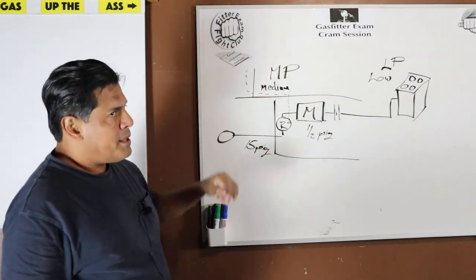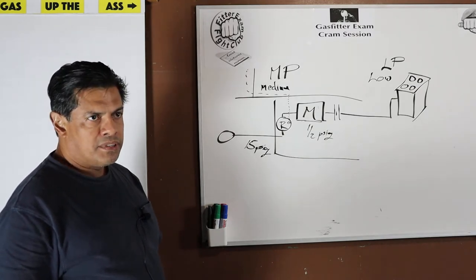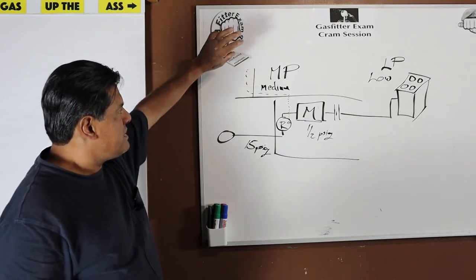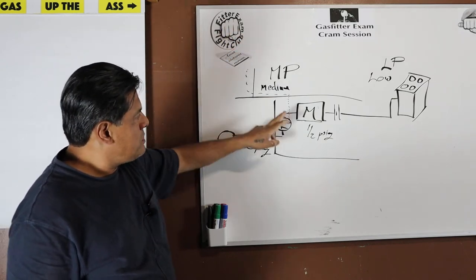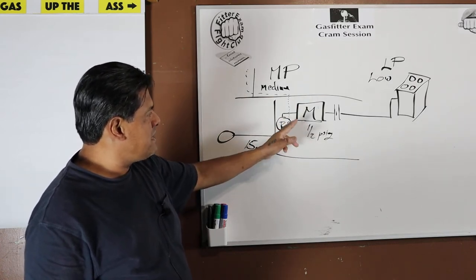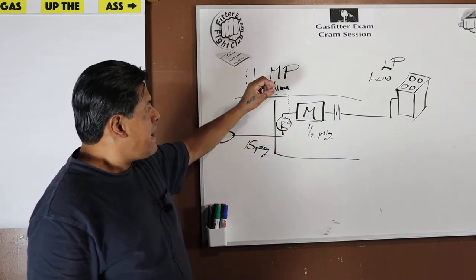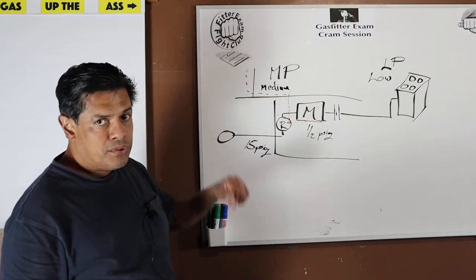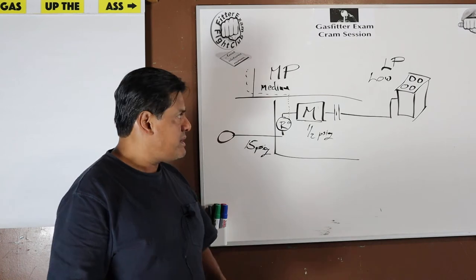You've seen them, though. They're little pipes, usually maybe 1 inch, 3/4, something like that, for apartment buildings. They could be bigger, but it's not a huge pipe. You maybe see one or two of them. You see the little cowls or the little vent caps on them. That is the vent to the tapping on the regulator, the vent tapping, so that if for some reason the diaphragm fails or the unit is overwhelmed in whatever way, any gas that's released is going to go in the vent and out to the open atmosphere. It's not going to start collecting in this enclosed space, which invites issues.